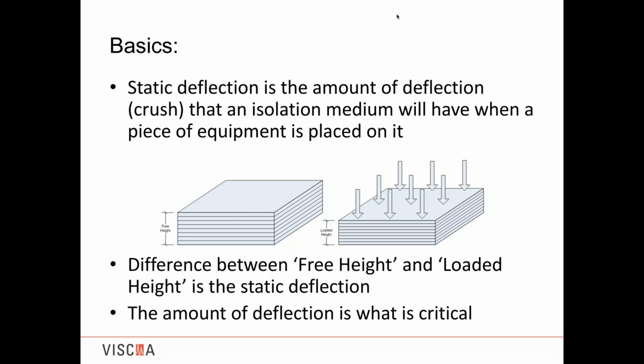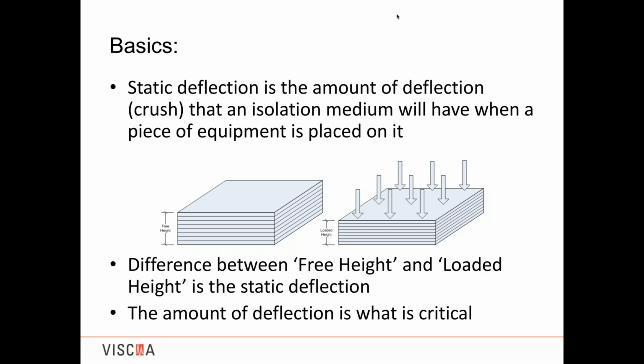And when I talked about 0.2 to 5 inches, that's what we're measuring. So obviously, if it's just a pad or a block of wood, you'll get hardly anything. If you've got a very tall spring, the spring can deflect on the order of magnitude of 4 or 5 inches, and you have a lot of deflection in your system. And it's the amount of that deflection which is critical to getting the isolation efficiency you'll be calculating later on through Angela.